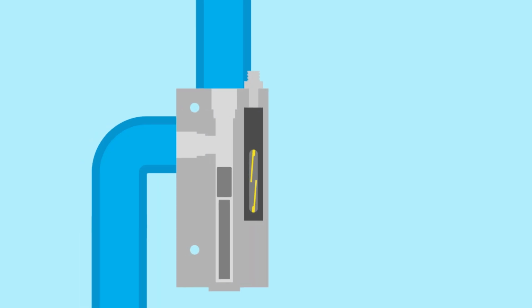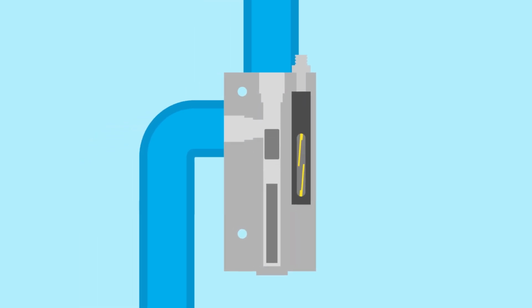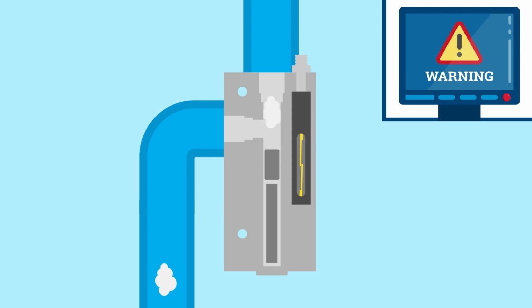The 125 series employs a magnetic piston in the flow stream that is suspended by the repulsion of a fixed magnet. If the flow rate increases, the piston moves against the repulsion of the fixed magnet and actuates the hermetically sealed reed switch, triggering an alarm or visual signal.